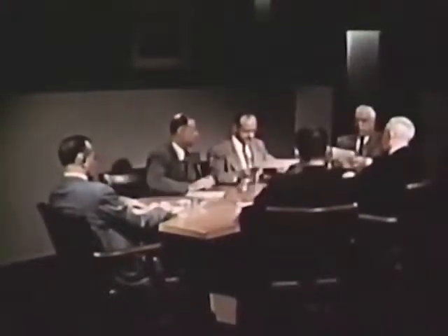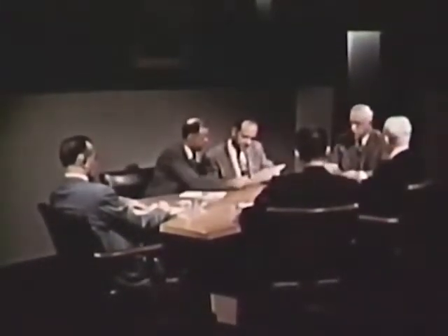I also have the engineman's statement on the fire on this locomotive. "I attempted to use the CO2 extinguisher, but the smoke was too thick. I didn't operate the CO2 valve to the high-voltage cabinet." Gentlemen, here it is again. On this particular locomotive, there is a CO2 nozzle built right into the high-voltage cabinet. But apparently in this fire, he did not know where it was.